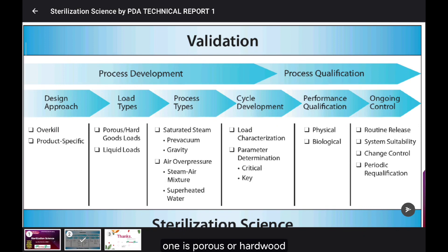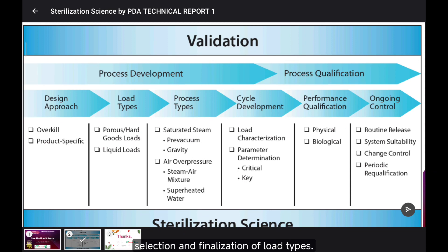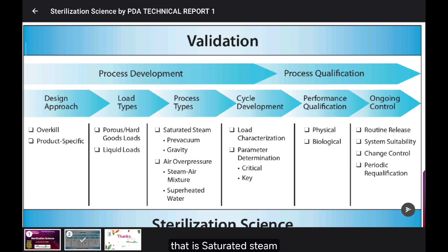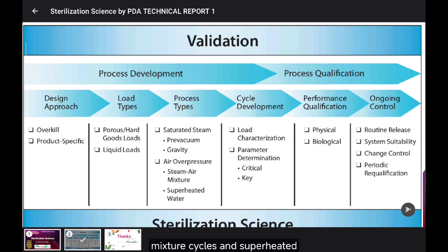After selecting the design approach, we need to finalize load types. The first one is porous or hard goods loads and the other is liquid loads. After selection and finalization of load types, we need to select the process type applicable for that particular load. For that load type, we select from different processes: saturated steam, pre-vacuum cycles, gravity cycles, air overpressure cycles, steam-air mixture cycles, and superheated water cycles.